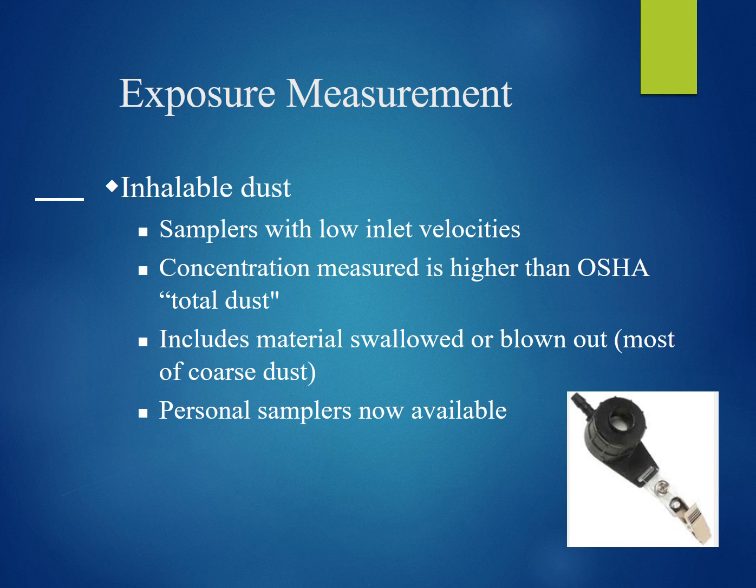It is important to note that using this sampler is not comparable to the OSHA total dust permissible exposure limit, because the fraction of dust that's collected with an inhalable sampler typically has a higher mass fraction, or weighs more, than the sample dust collected using the NIOSH 500 method that we mentioned earlier.